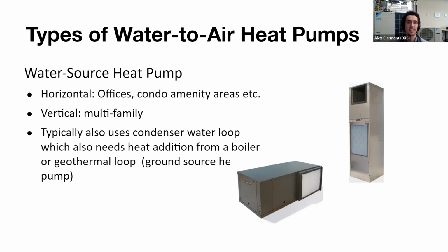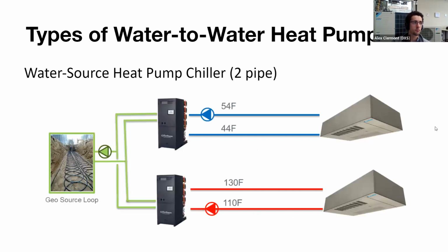Again, here everything is in this machine. So all the compressor, condenser, evaporator will be connected to water to be used to reject and absorb heat through a condenser water loop. If the condenser water loop is a geothermal system, as we previously mentioned, then we call these types of heat pumps ground source heat pumps. Next, we'll get into water-to-water heat pumps.